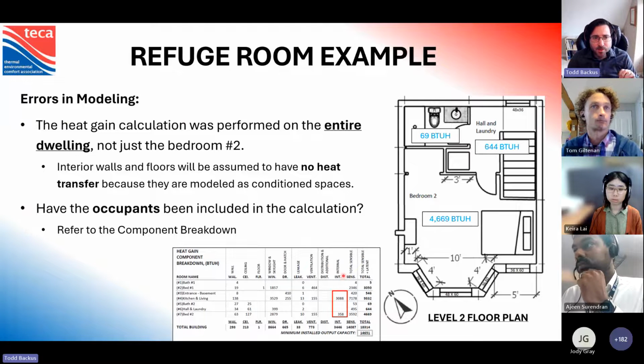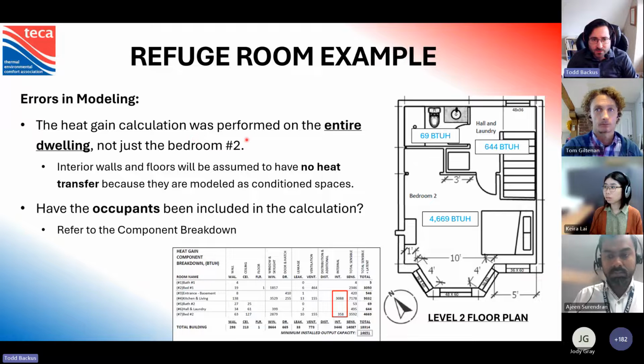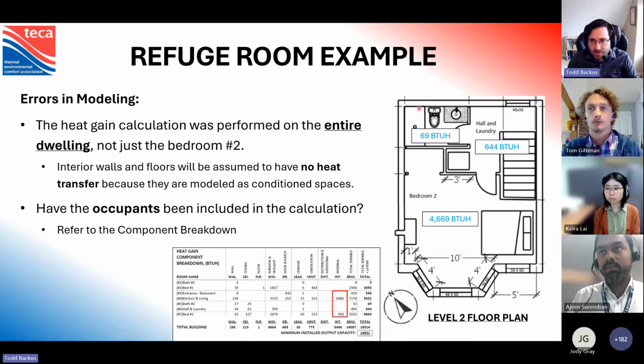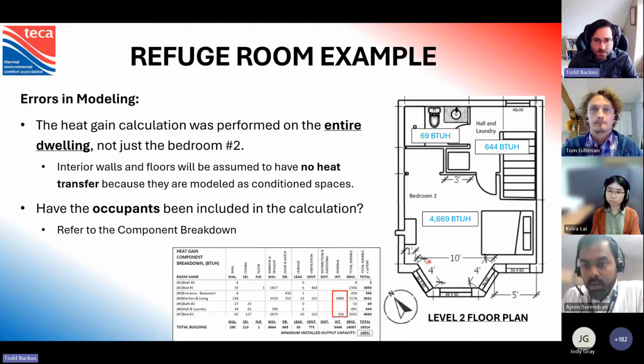In this example, the heat gain calculation was performed on the entire dwelling, not just bedroom 2. So they've modeled that there's cooling coming in here, there's cooling coming in here, in the floor below, in the entire dwelling, and then they're just cherry picking this one number for this bedroom. So they're ignoring all of the heat transfer through these interior walls and through the floors.